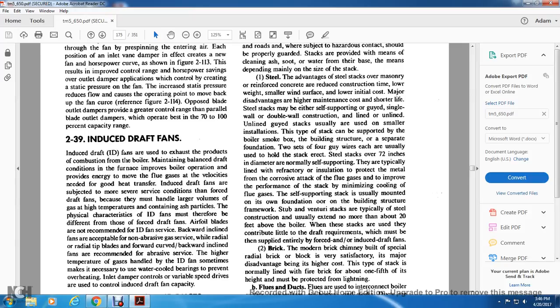This type of stack can be supported by the boiler smoke box, the building structure, or a separate foundation, with two sets of guy wires, each usually holding the stack erect. Steel stacks over 72 inches in diameter are normally self-supporting. They are typically lined with refractory insulation to protect the metal from the corrosive action of flue gases and to improve performance by minimizing the cooling of the flue gases.